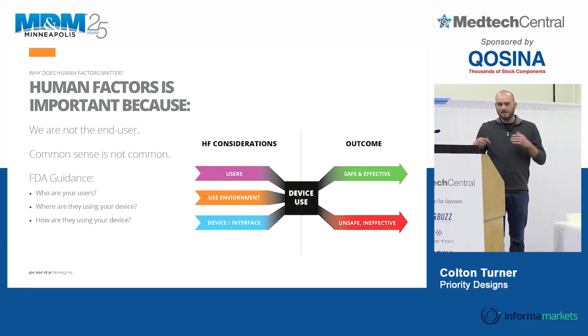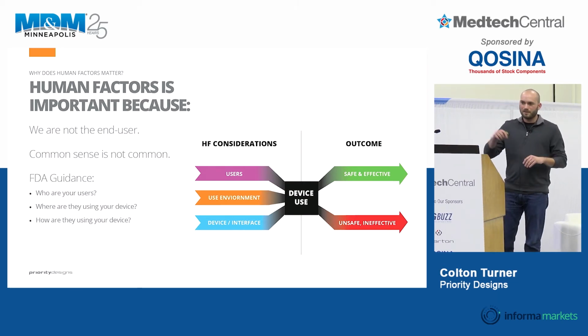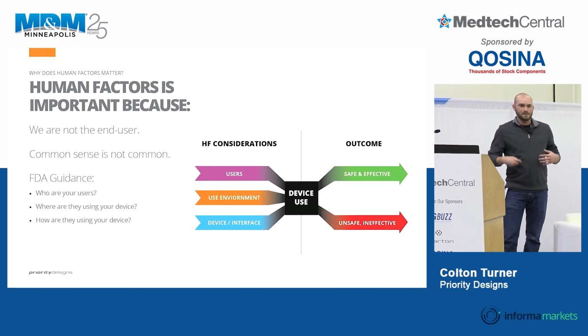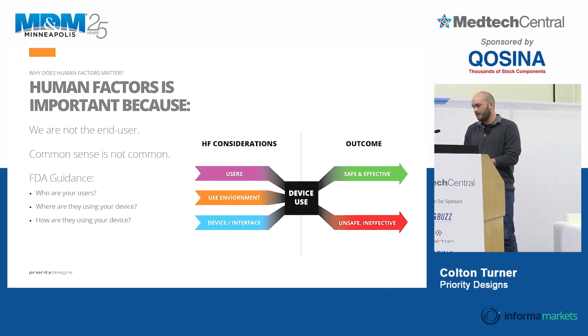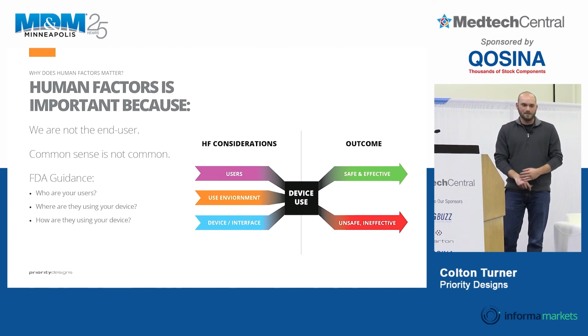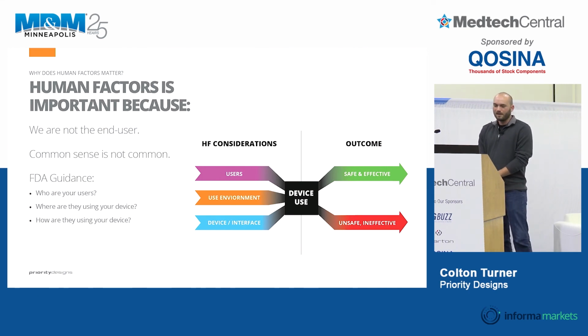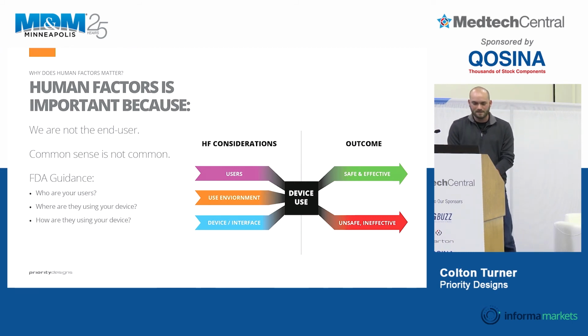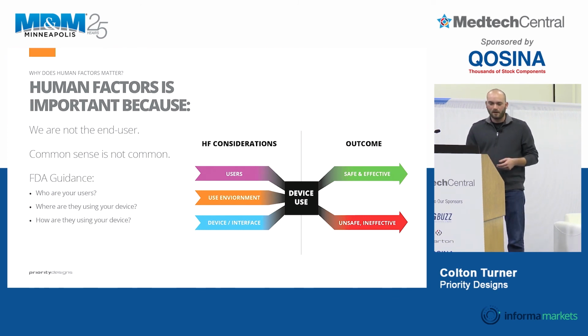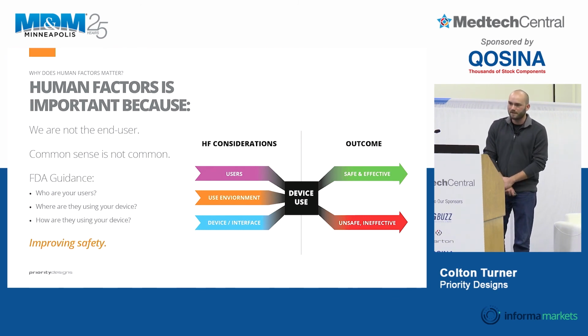And so human factors seeks to bridge that gap between design and engineering and the user to make sure everybody's on the same page and everybody's using those interfaces in the same manner. And then specifically with medical devices, the importance of human factors comes from regulatory agencies like the FDA, where the FDA is now strongly recommending, if not mandating, that human factors validation studies be done to prove that risk and safety have been mitigated within medical devices. And the way that we do that is through an understanding of who our users are, where they're going to be using a device, how they're going to be using the device. And all of that is meant from the FDA's perspective to improve safety and mitigate risk.